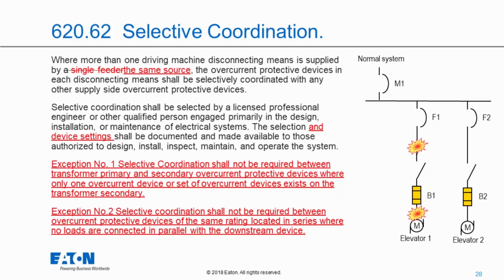Codemaking Panel 12, who handles Article 620, felt it was important to further clarify that the device settings are also important to be documented, and that would be especially true when it comes to circuit breakers that have perhaps electronic trip units where you have multiple settings that are required to be set. They also put 2 exceptions in there that are similar to what's located in other parts of the code, other articles that require selective coordination.